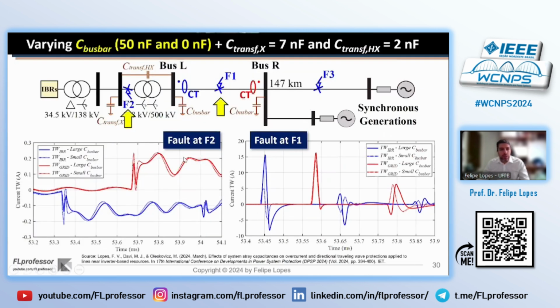Just to see when we change the stray capacitances for fault F2, for instance, a little bit change. There is a minor variation here in the wavefronts, the filtered signals. But when we consider the variation of the busbar capacitance here, we can see for our internal fault, the measurements change a lot their amplitudes here, which is cause of concern, at least for applications that consider measurements on the IBR side.